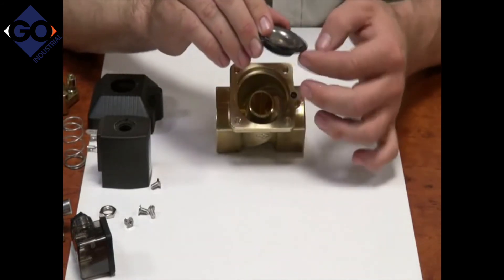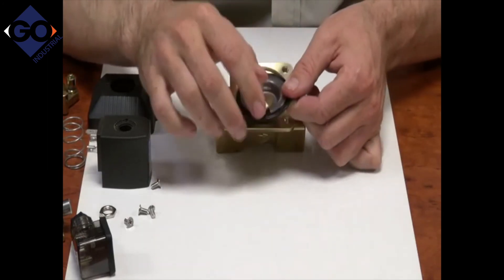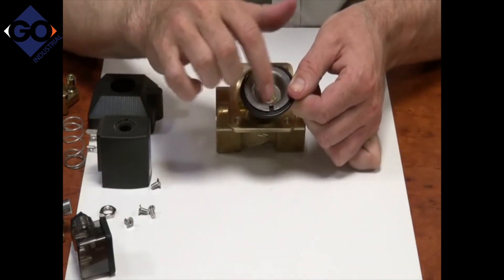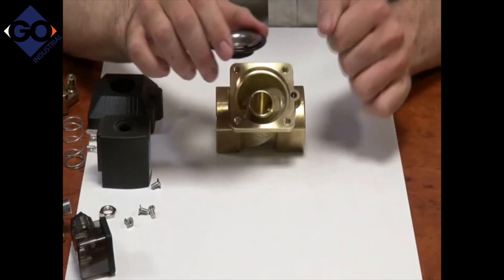Here's your diaphragm with a stainless steel plate. This is one of your bleed holes which lets pressure onto the top of the diaphragm. You probably can't see it - it's a very minute hole. It's important for that to be free.